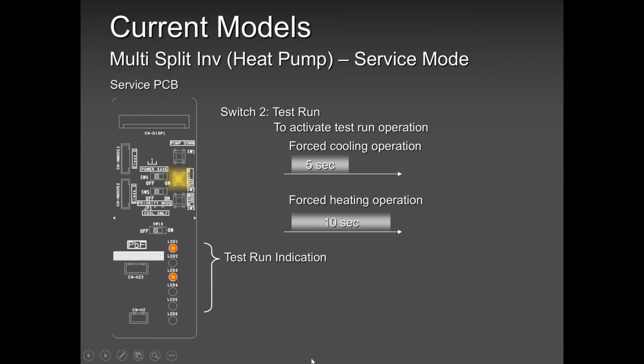Because I'll tell you one thing, at the terminal block it gets confusing which wire came from where, when all the 5 wires are in, all the 6 wires are in. If it's a 2-zone, it's not a problem, it's easy. But if it's a 3, 4 or 5, it gets complicated, too many wires, you know. So test run, in my opinion, in my experience, only use it when you're troubleshooting. You are called for low on refrigerant or for whatever reason. And if you need to cancel it, just press it again and you're done.